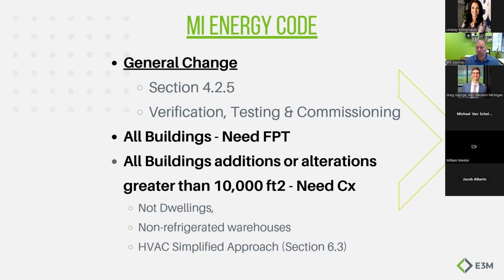For example, with an outdoor air economizer that brings in fresh air for free cooling on an HVAC unit, functional performance testing means simulating the conditions to make sure that damper opens, the fresh air comes in, and it closes at the right temperature. You're essentially going system by system, verifying it's operating the way it's intended to.